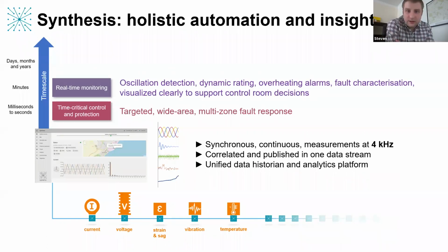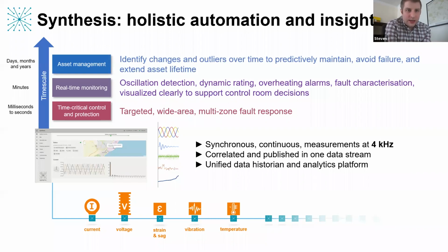We can also build upon that less time critical, but also quite important functions such as detection of oscillations in the system, which has been quite important in the past year, particularly in the UK, and things like dynamic line rating. It's relatively easy for us to build that in because we've got direct access to current measurements and spot temperature measurements, and additional measurements such as strain and sag are also possible, which can be important. And taking the bigger picture, we can also help with long-term objectives, such as maximizing the life of assets and looking for signs of aging that were invisible before because the sensing infrastructure was too costly or impractical.